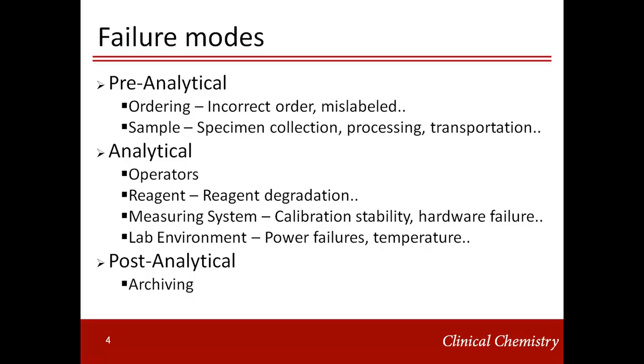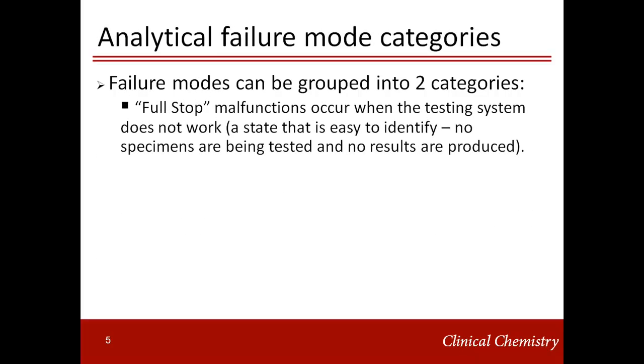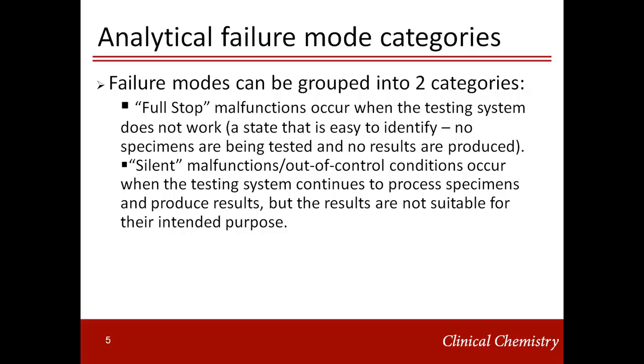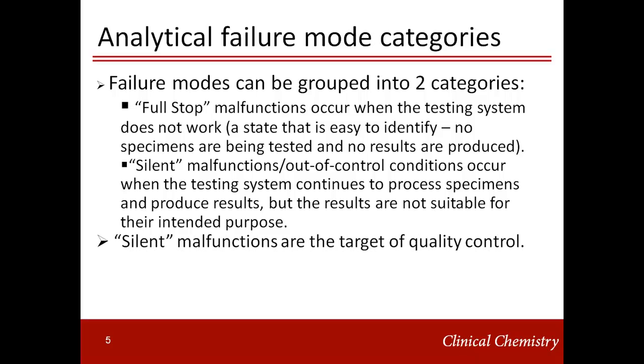Now let's talk more about these analytical failure modes. Failure modes can be grouped into two categories: full-stop malfunctions or silent malfunctions. Full-stop malfunctions occur when the testing system does not work — these are easy to identify because testing is stopped and no results are produced. However, we are not so lucky with silent malfunctions. These silent malfunctions lead to out-of-control conditions where the testing system continues to process specimens and produce results, but these results are not suitable for their intended purpose. These out-of-control conditions are hard to identify and are the target of quality control.